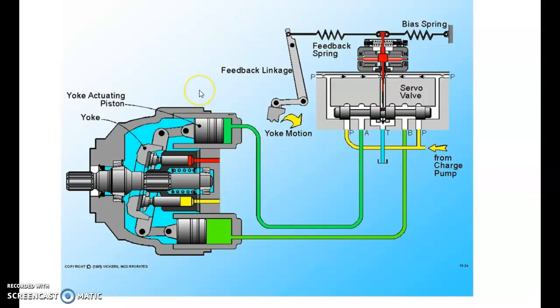That's a little bit manufacturer specific to Sundstrand, but ultimately all manufacturers of hydrostatic drive pumps are going to have an electronic version where solenoids control pilot pressure to either two single acting servo cylinders or one double acting servo cylinder that's going to move the swash plate.